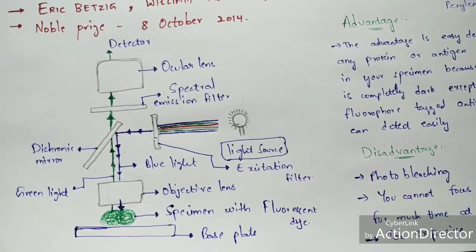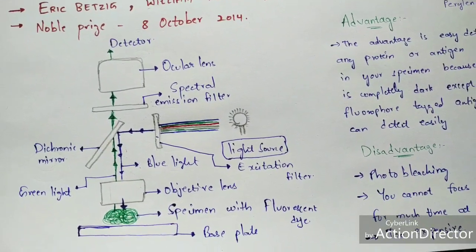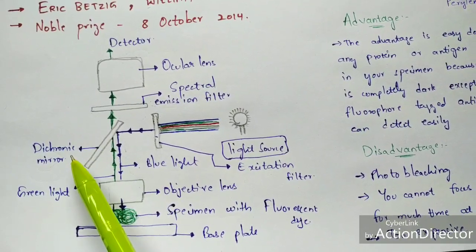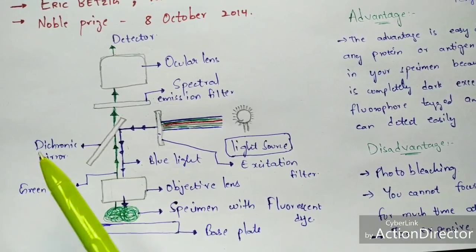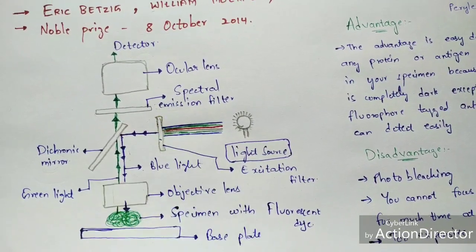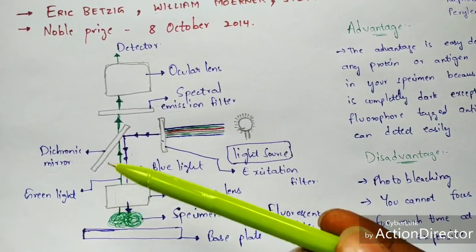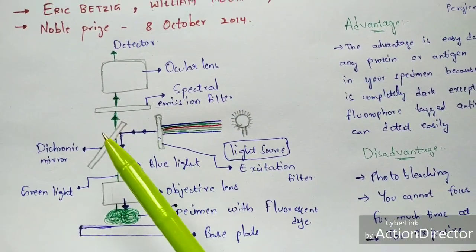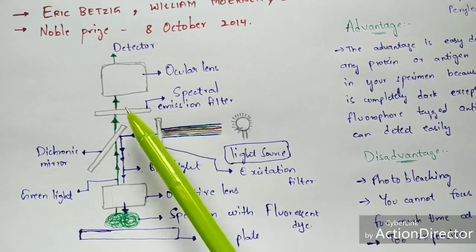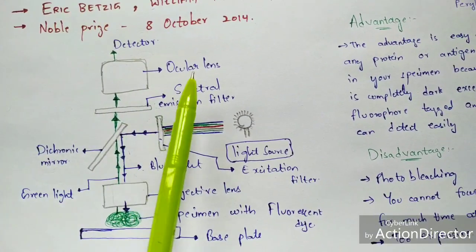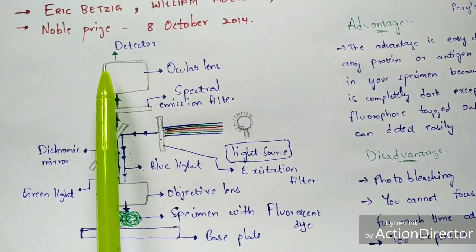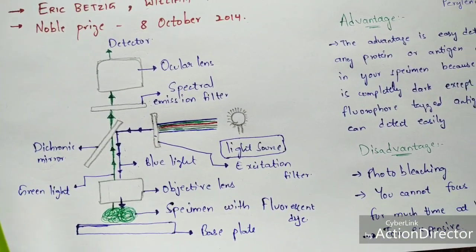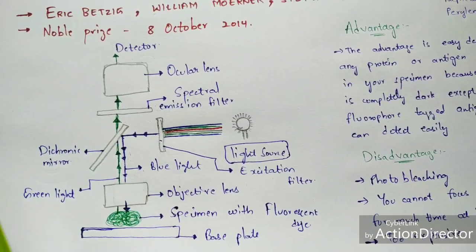The major function of the spectral emission filter is to detect and block the remaining blue color light that has passed through. Only the pure green color light is allowed to pass to the ocular lens. From the ocular lens, the signal is sent to the detector, which forms the image. We can then see the image formed on the detector.